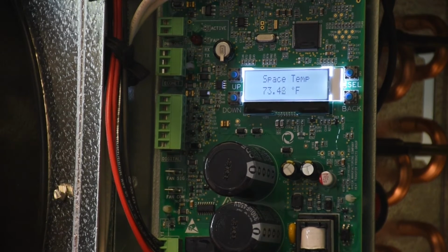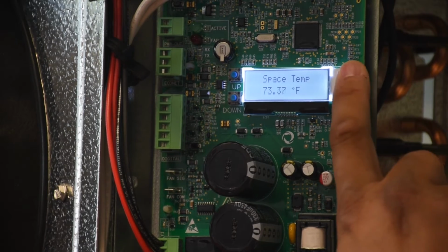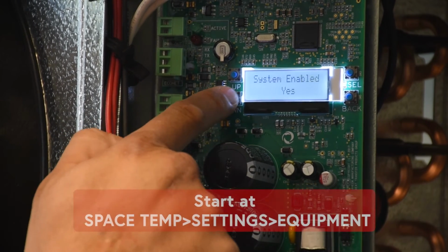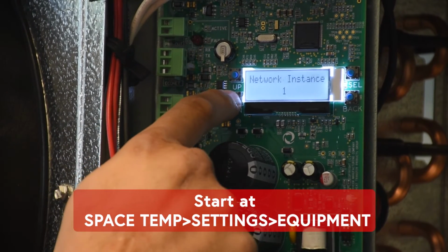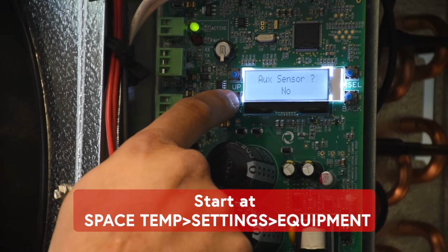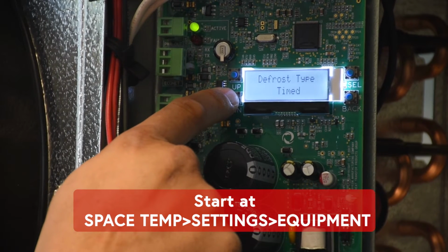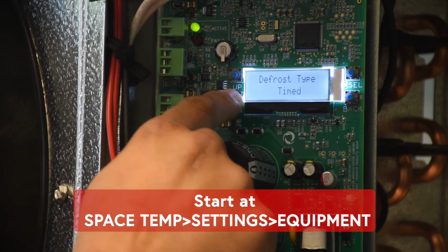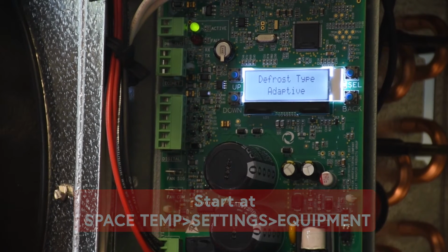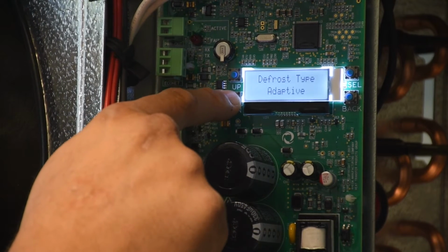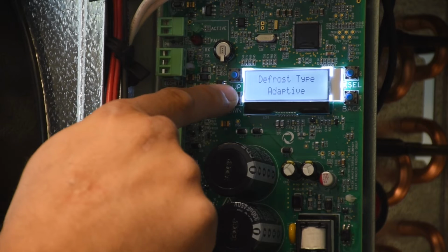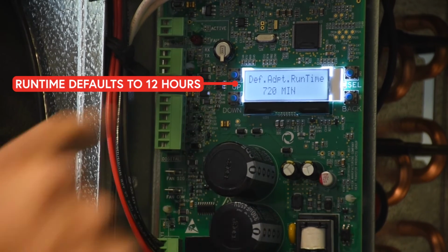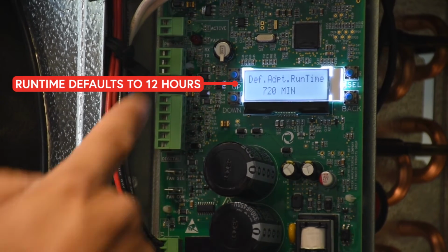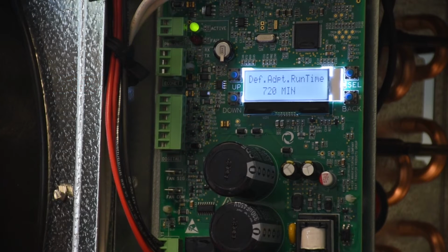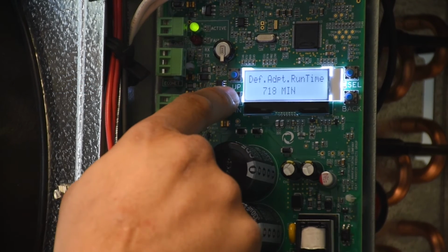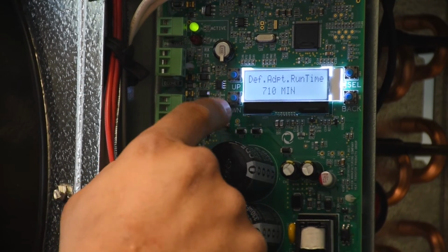Now to change the maximum runtime for adaptive defrost, navigate to your settings, scroll down to equipment, and of course for adaptive defrost is where this other runtime setting would apply. So the setting has to be on adaptive, and then your adaptive defrost runtime defaults to 12 hours, and then of course you can adjust it from there.